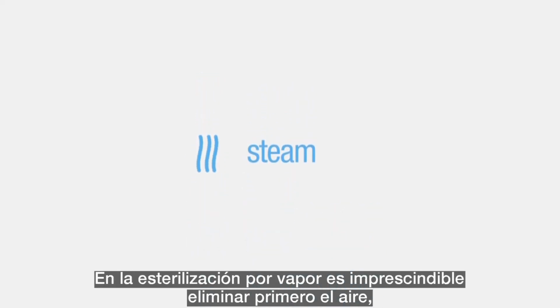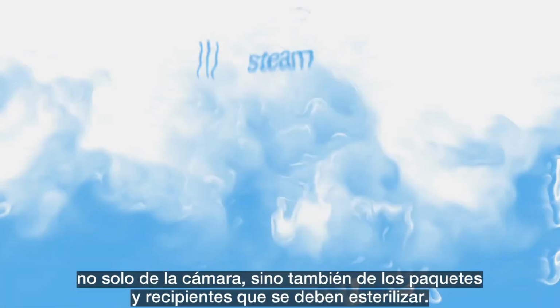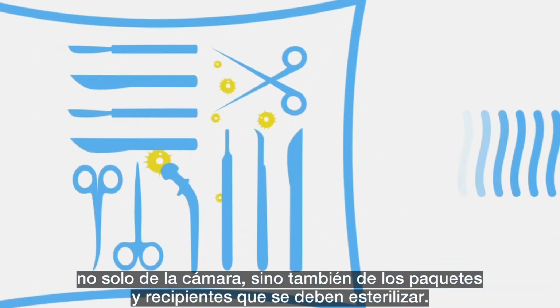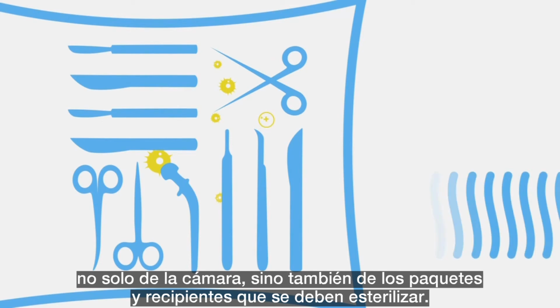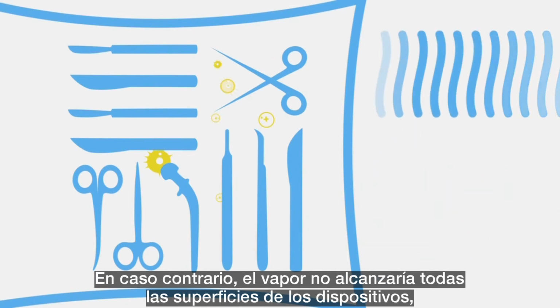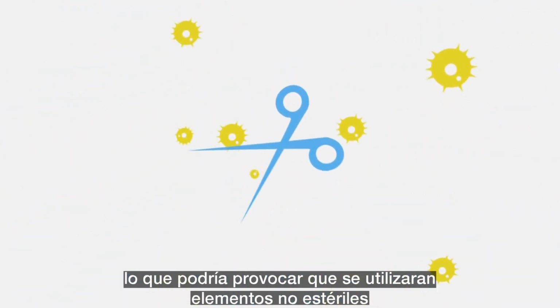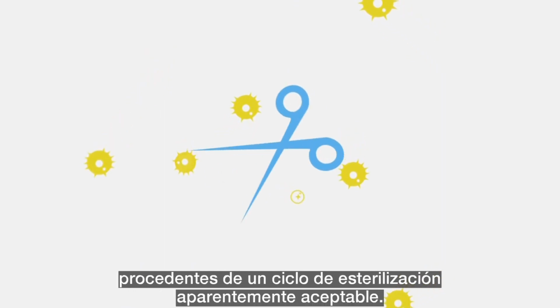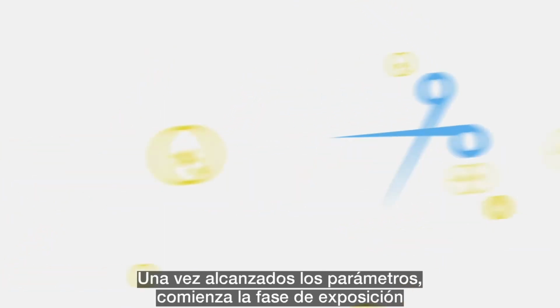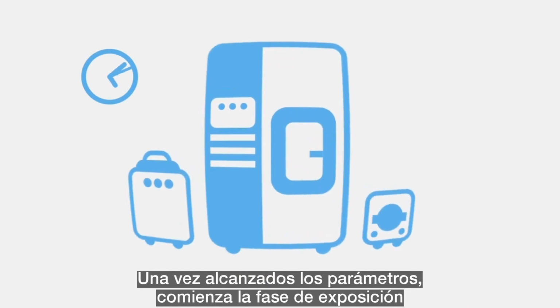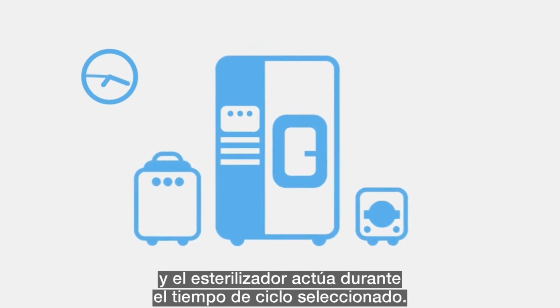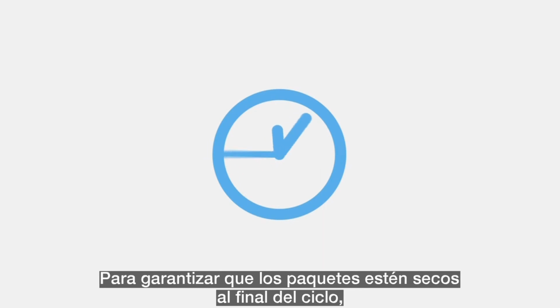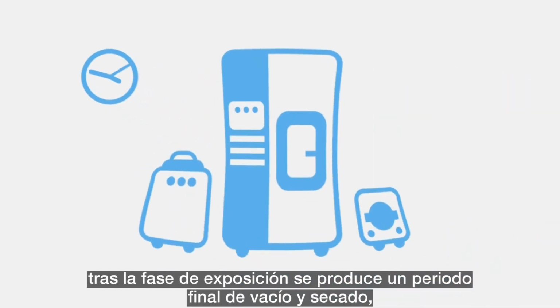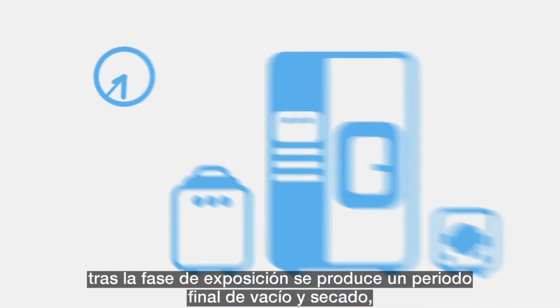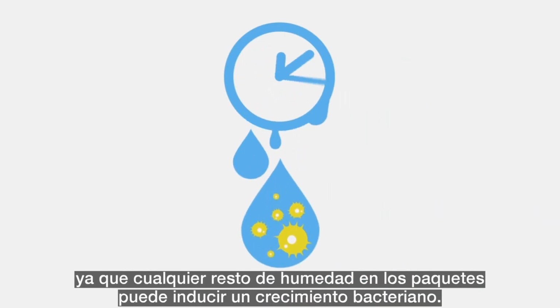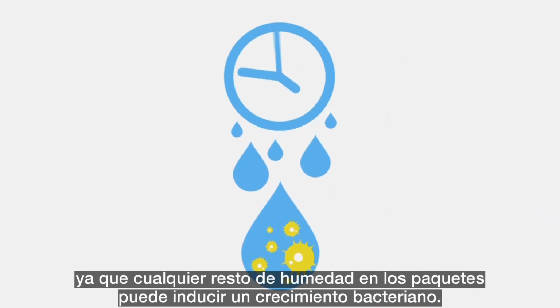When sterilizing by steam, it is imperative to first remove air, not only from the chamber, but also from the packs and containers being sterilized. If you don't, steam might not reach all device surfaces, which could result in non-sterile items being used from a seemingly acceptable sterilization cycle. Once the parameters are reached, the exposure phase begins and the sterilizer runs for the selected cycle time. To ensure packs are dry at the end of the cycle, the exposure phase is followed by a final vacuum and drying time, because any moisture on the packs can lead to microbial growth.